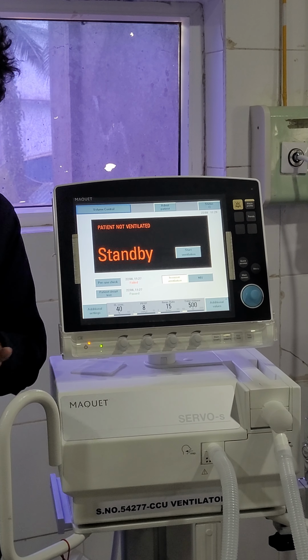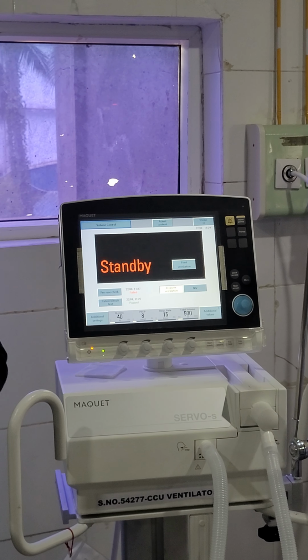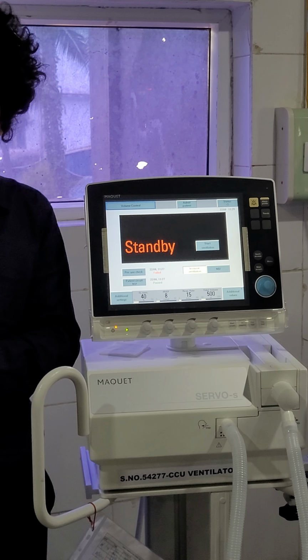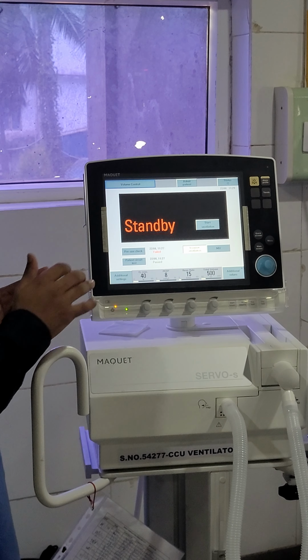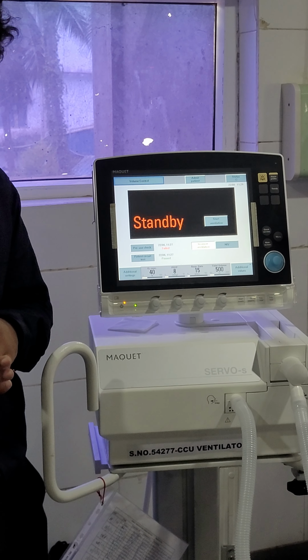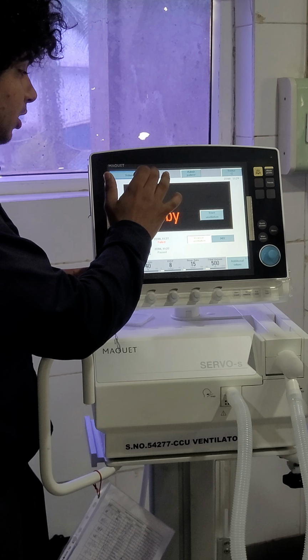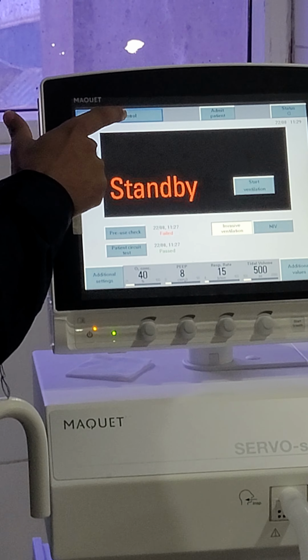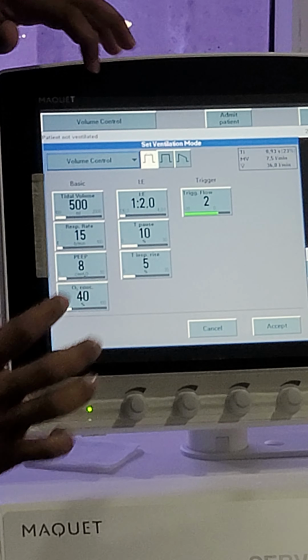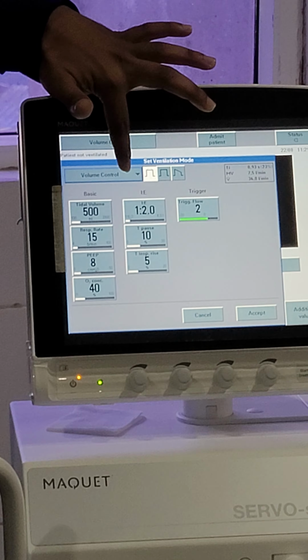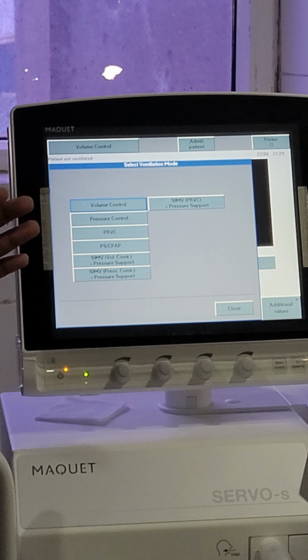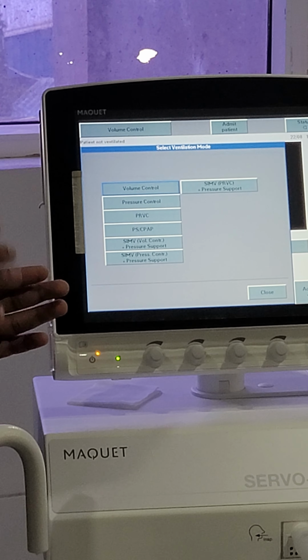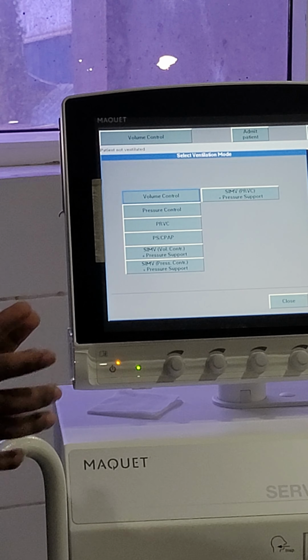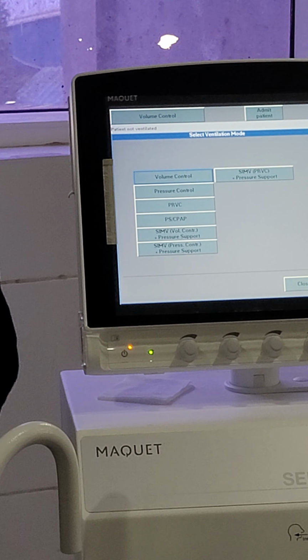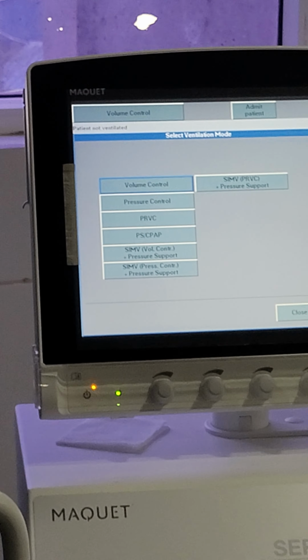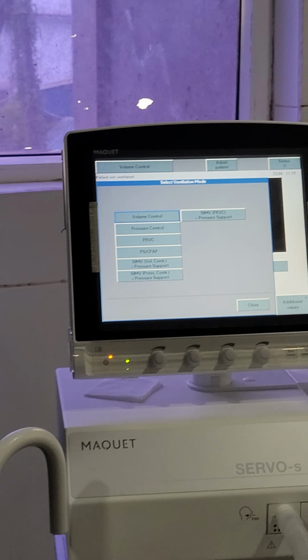So the tidal volume of Servo is 1000 ml. From 10 kg to 50 kg you can use the ventilator. It can be used for invasive, it can be used for non-invasive. To go for modes, you have to press at this side of the ventilator, and based on the condition of the patient you can select the modes. Volume control, pressure control, PRVC, pressure support, SIMV volume control, SIMV pressure control, and SIMV PRVC is given with Servo.